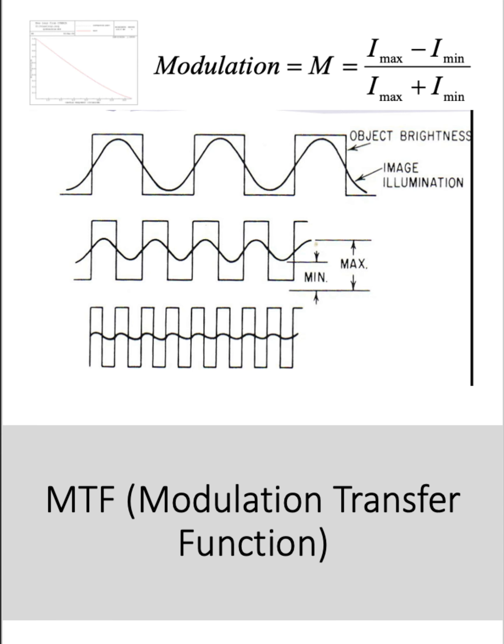This idea becomes really interesting and relevant when extended to the idea of resolving spatial frequencies. When imaging, these line spread functions overlap and create a wavy pattern that can reduce the modulation and make it harder to resolve the image. This concept is characterized by something called a modulation transfer function, or MTF curve. The MTF curve describes how well an optical system will perform as a function of the spatial frequency that it's trying to image.